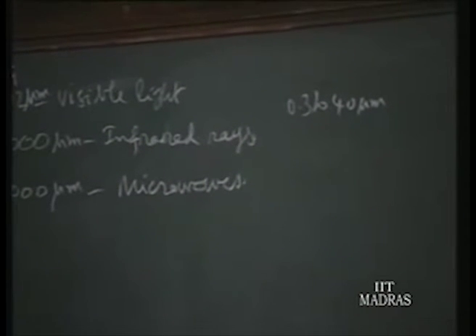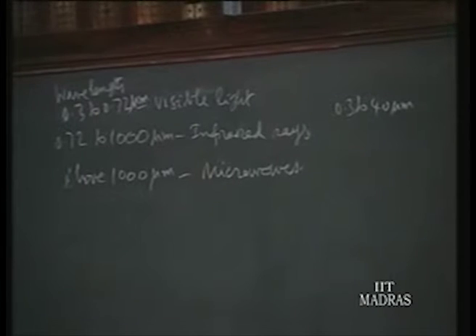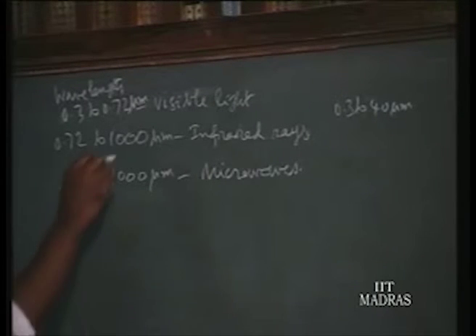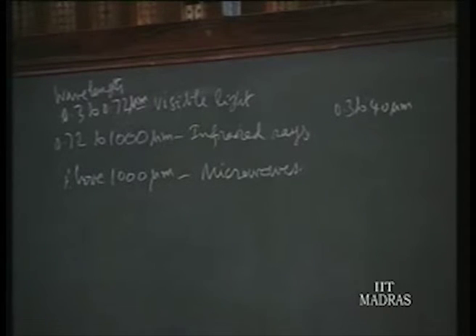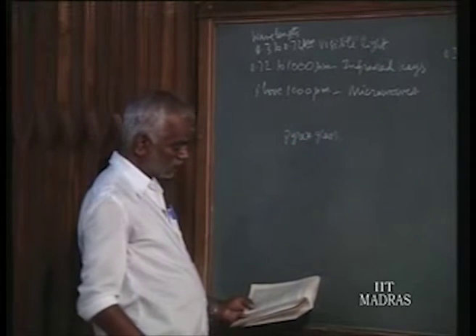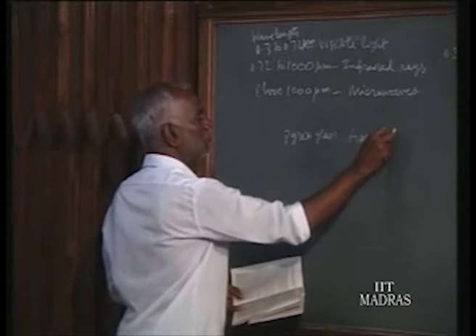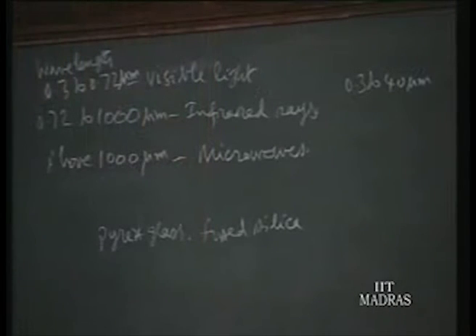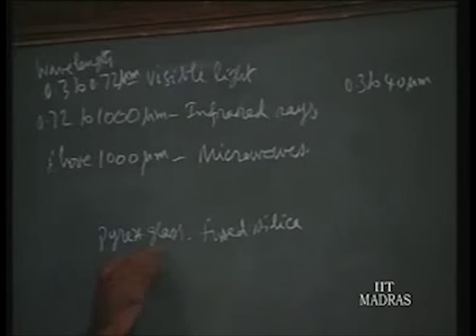The radiation thermometers use the wavelength range of 0.3 to 40 microns, containing both visible and infrared regions. Ordinary glass, used for visible light, is opaque for infrared rays. Hence the lenses for these radiometers are made up of Pyrex glass, fused silica, and calcium fluoride — special glasses that can transmit infrared rays. Above 1000 micron wavelength, the electromagnetic waves are microwaves.